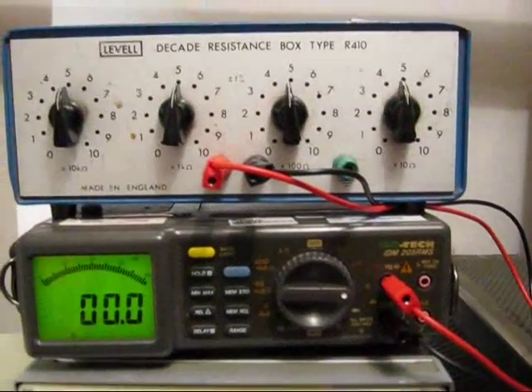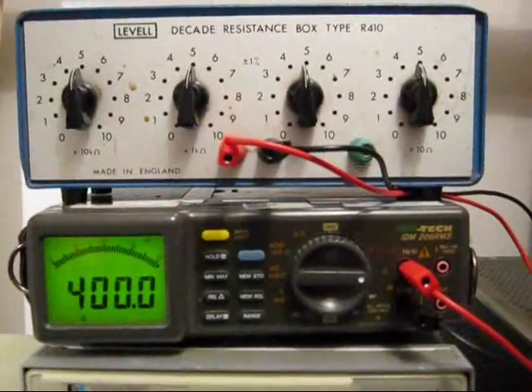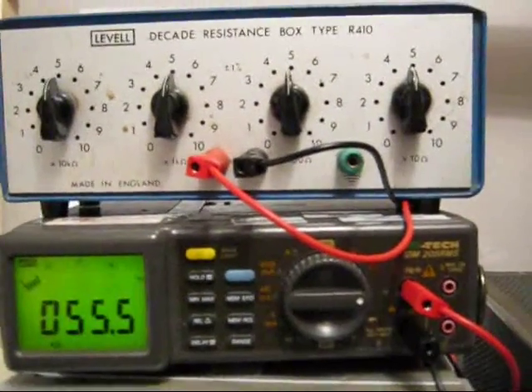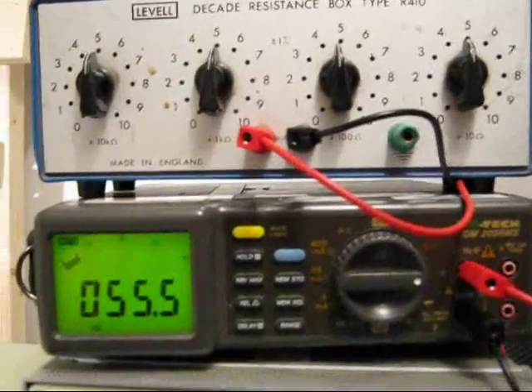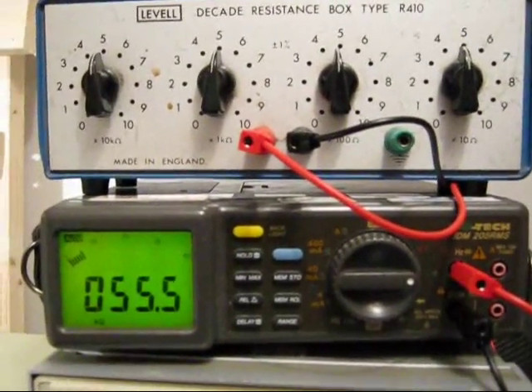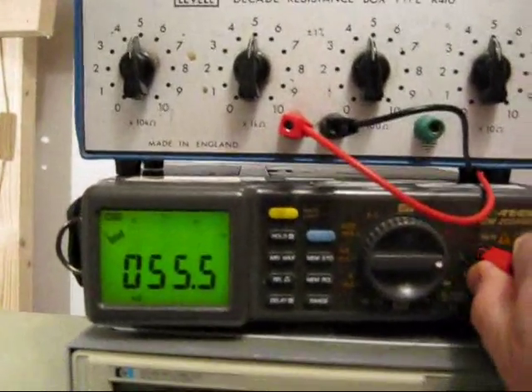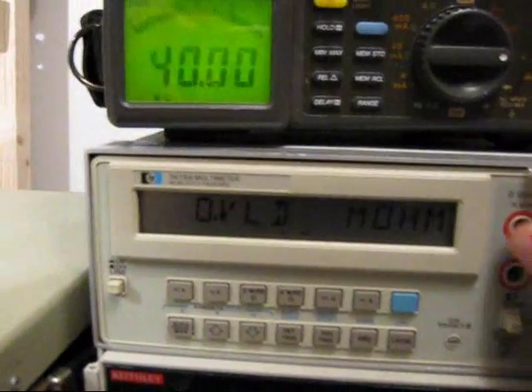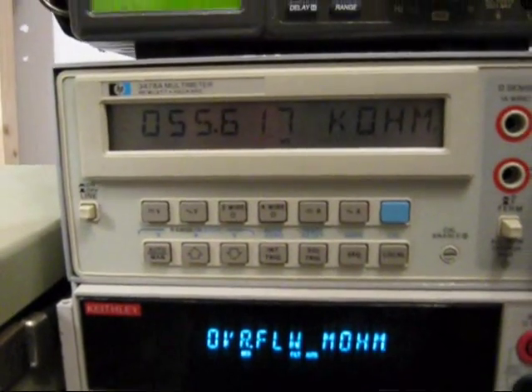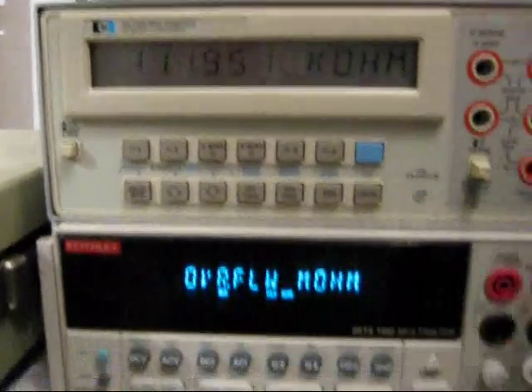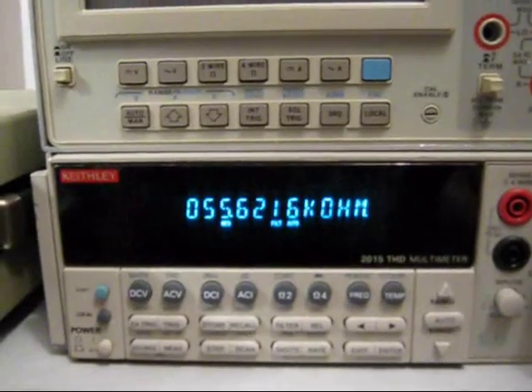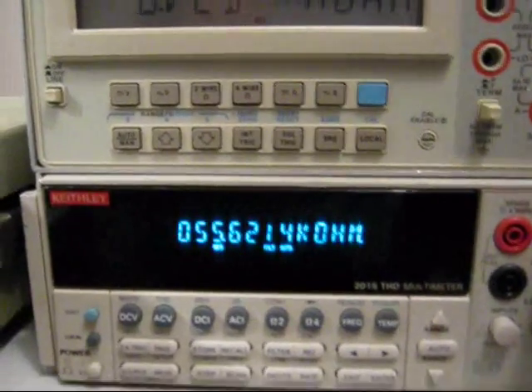Let's have a look at measuring resistance. Just set up an R box. I've just set up an R box to 55.55 kilohms. It's not a particularly brilliant R box, but you can see that the Isotec is giving a sensible reading with it. And if I plug in the HP, you'll see that's showing 55.61, and the Keithley is showing 55.62.